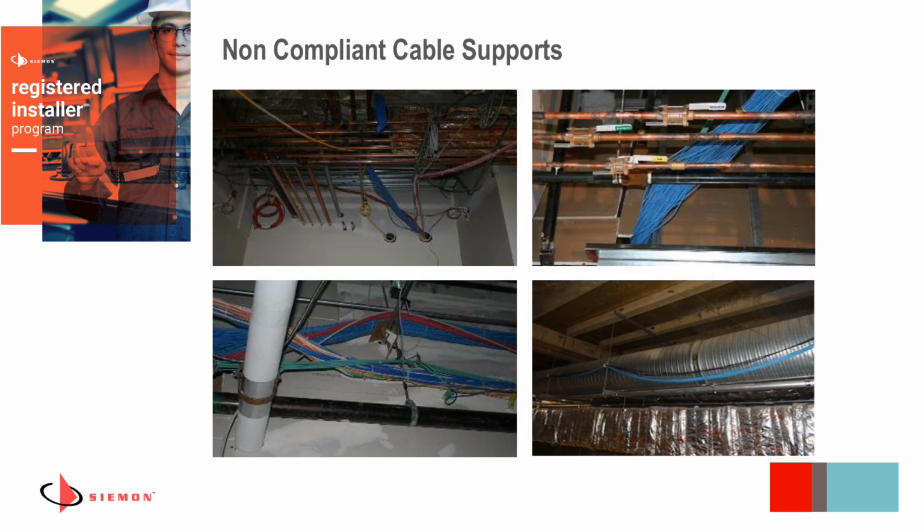Now here you might think some of these examples are a little bit extreme, but it's actually not that uncommon for us to come out to the field to do audits and find situations like this. In some cases, installers, maybe they're running late on the project, maybe they're over budget and didn't want to put in the required supports, but you'll see more of this than you'd like to see perhaps up in the ceiling. It's important to be avoided, because other trades are going to be up there in this space.